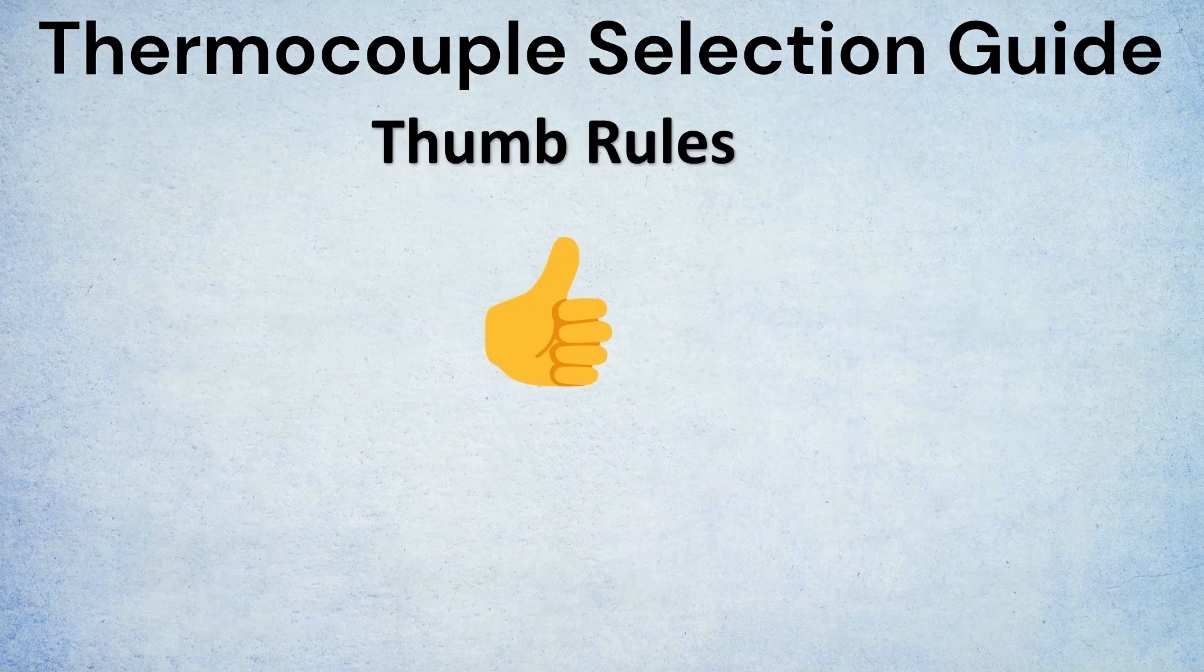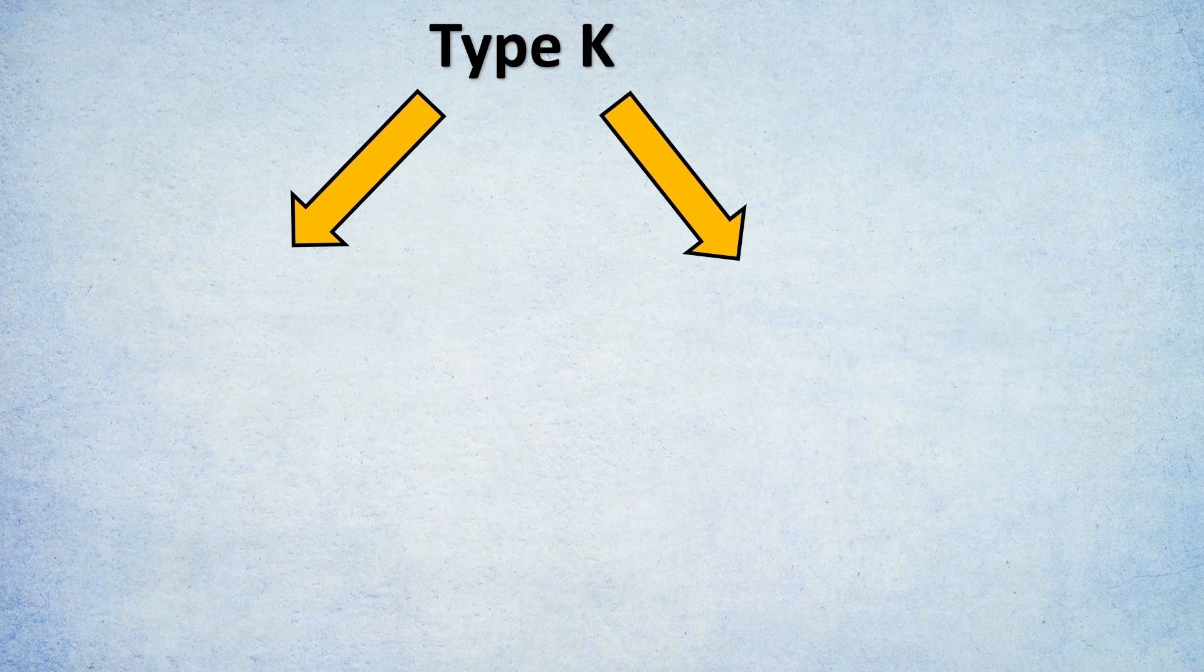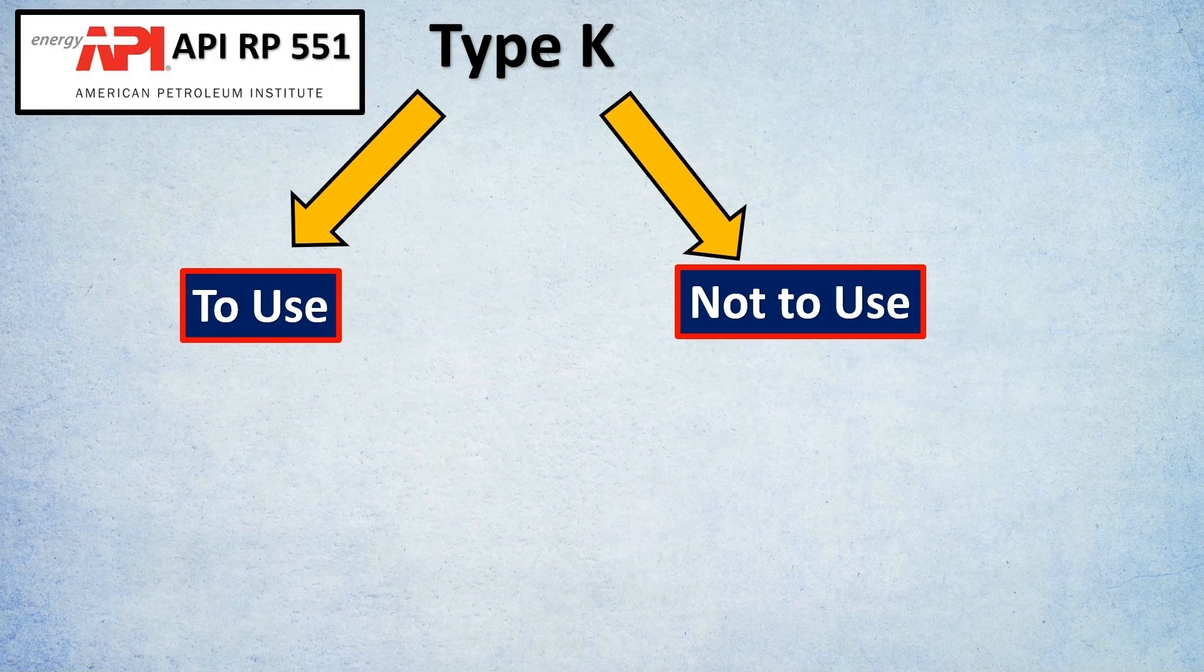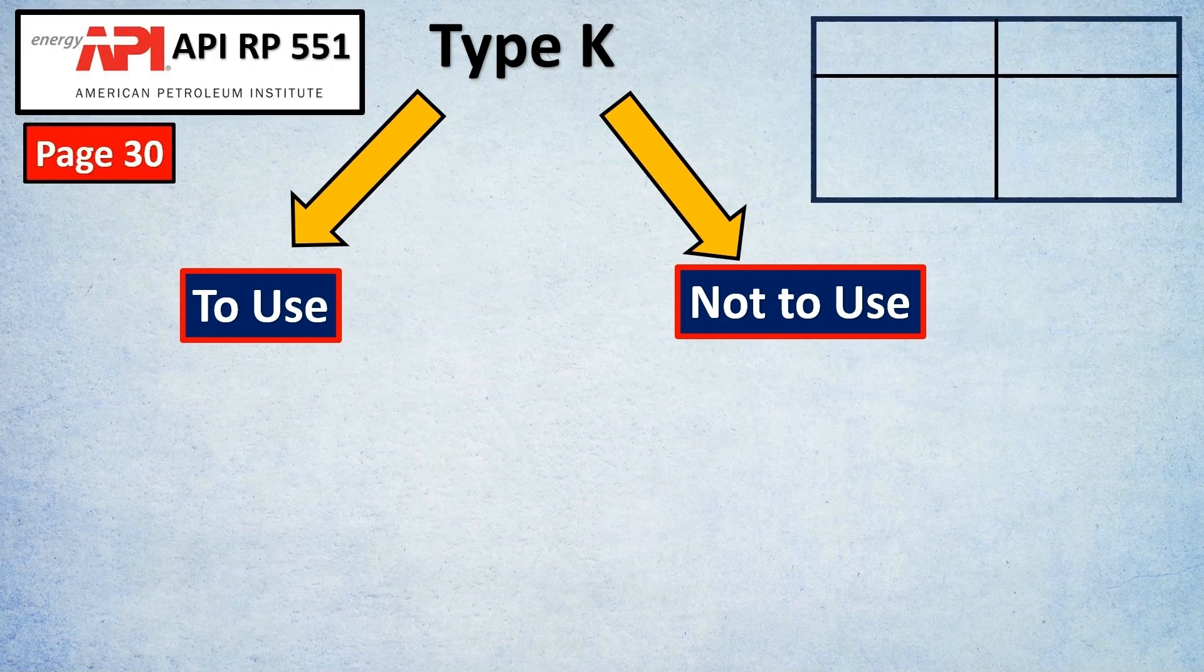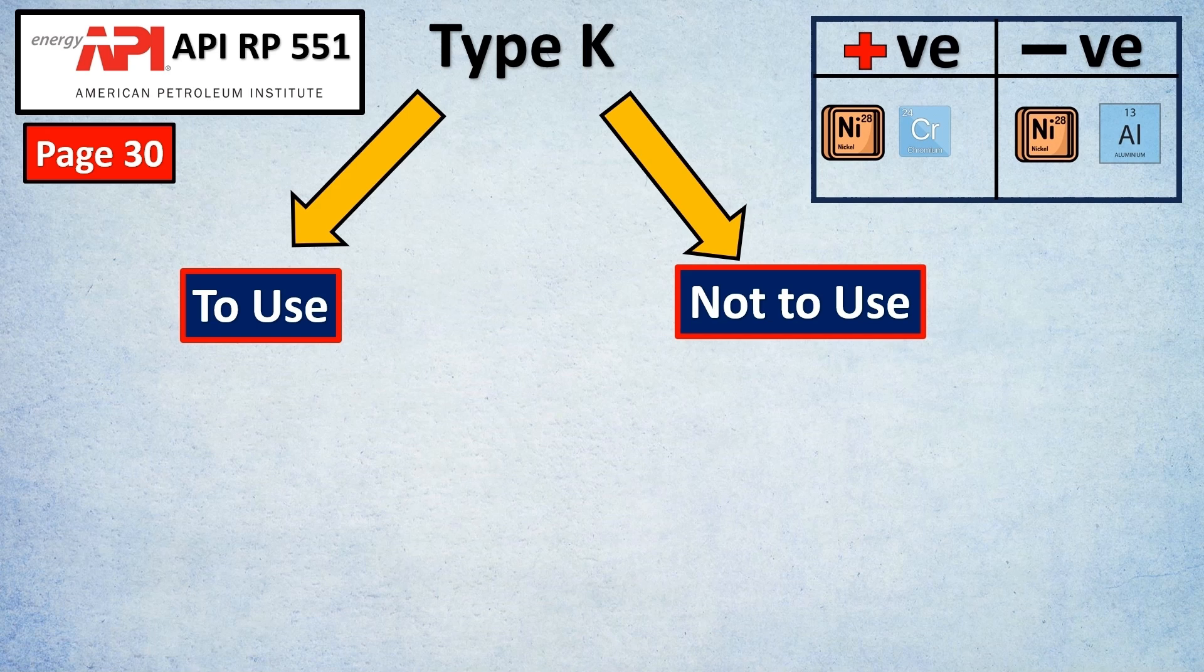Let's look at thumb rules for selecting which type of thermocouple to use. Type K thermocouples are the most widely used. We'll look at when to use and when not to use these as per API RP 551 page 30. Type K has a positive side made of nickel-chromium and the negative side made of nickel-aluminum.